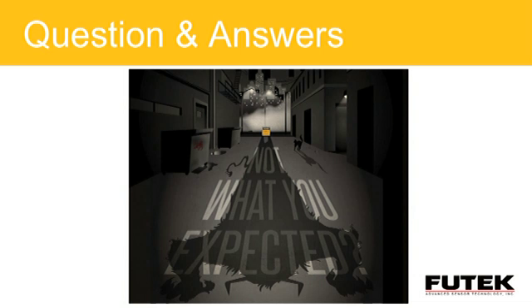Absolutely. I think if they have some type of verification interval, it's dependent on how critical their project really is. Is it so critical that they can't be more than 0.1% out? Do they have some extra room where the sensor's accuracy is over-designed for the product? The customer should really look at that part of it and make that determination. Over the years, as they use the product and perform their own verification or calibration, they'll be able to really determine what their true interval is.